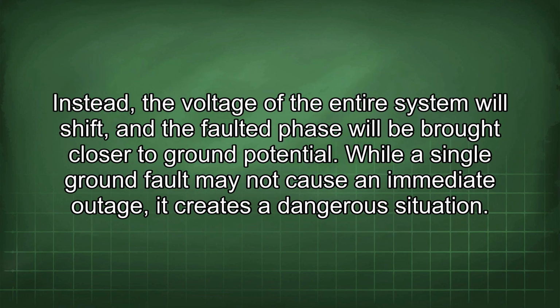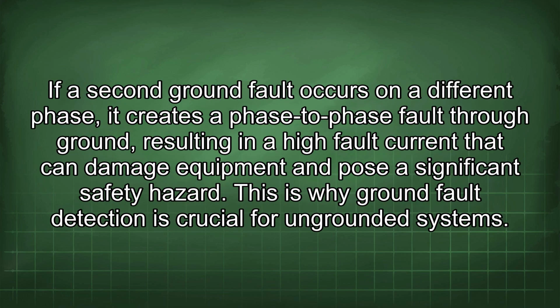Instead, the voltage of the entire system will shift and the faulted phase will be brought closer to ground potential. While a single ground fault may not cause an immediate outage, it creates a dangerous situation. If a second ground fault occurs on a different phase, it creates a phase-to-phase fault through ground, resulting in a high fault current that can damage equipment and pose a significant safety hazard. This is why ground fault detection is crucial for ungrounded systems.